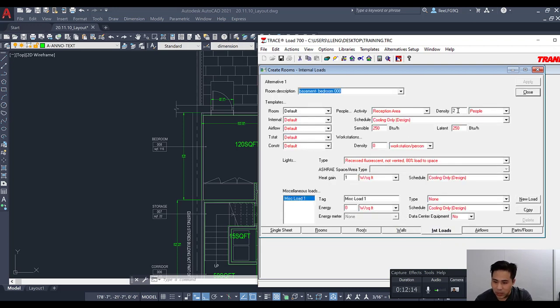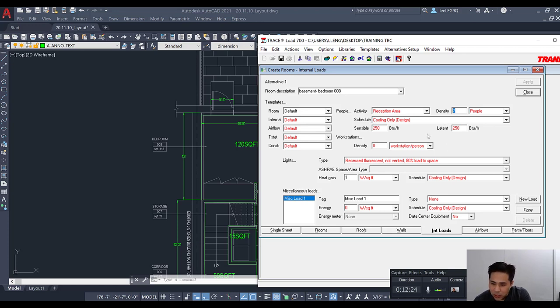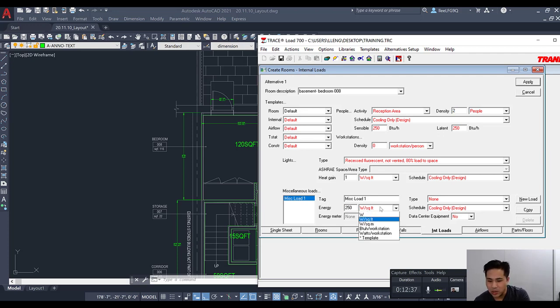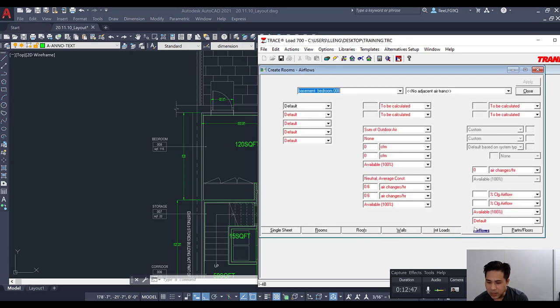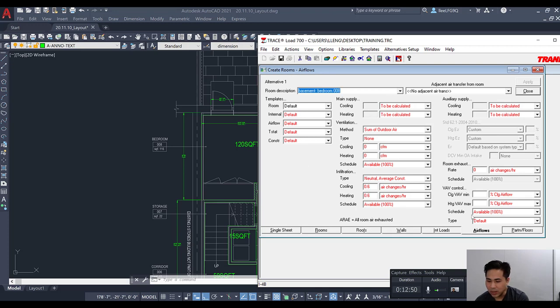For the internal load, we'll leave it at 2 people since it's a bedroom and typically up to two people could be in that room. The lighting default of one watt per square foot is a good value to keep. For miscellaneous loads, we'll add one computer at approximately 250 watts. The airflow tab can be left as-is.